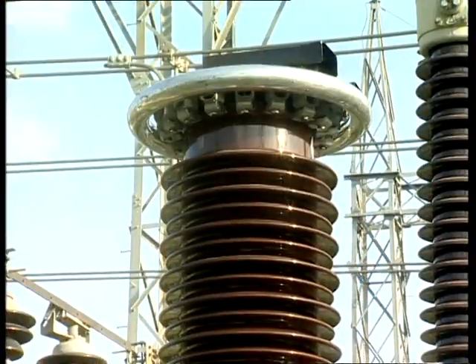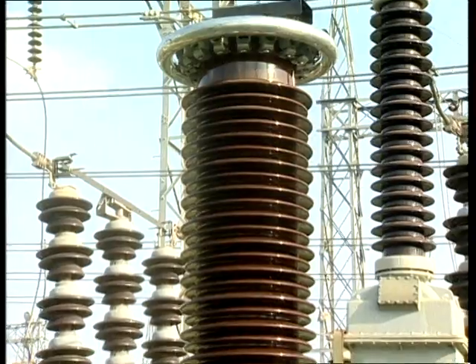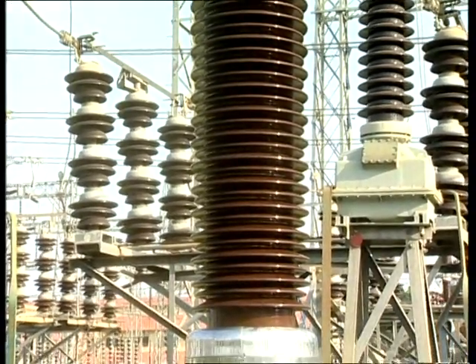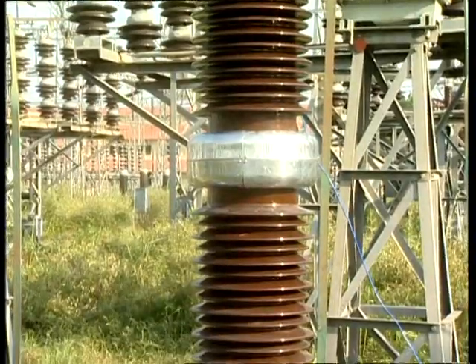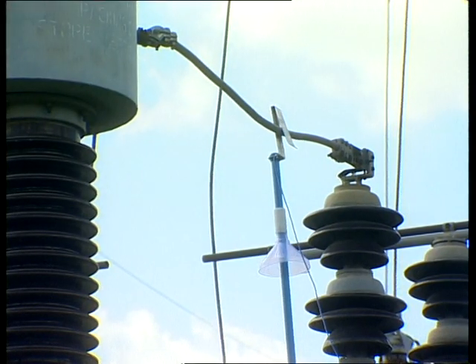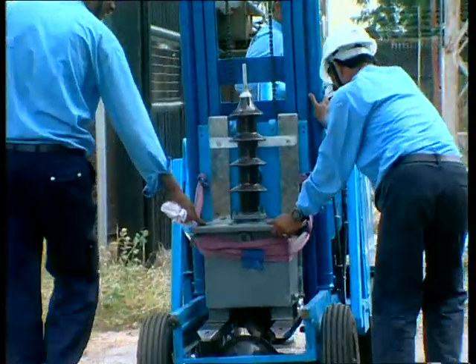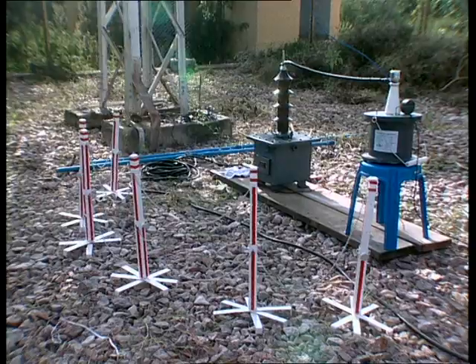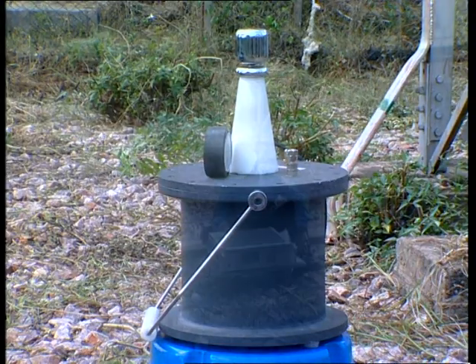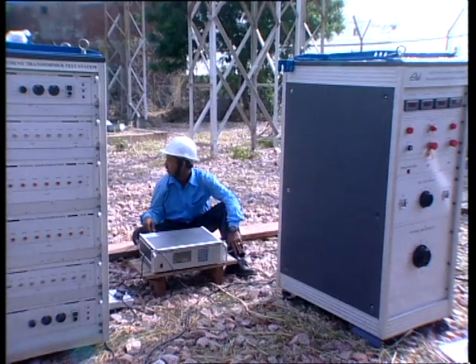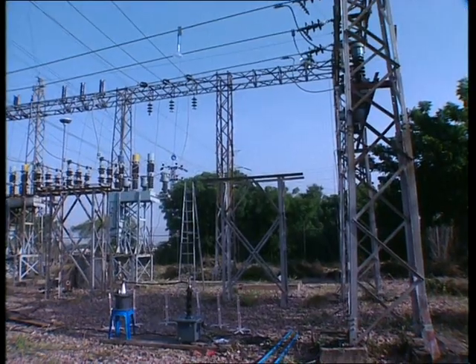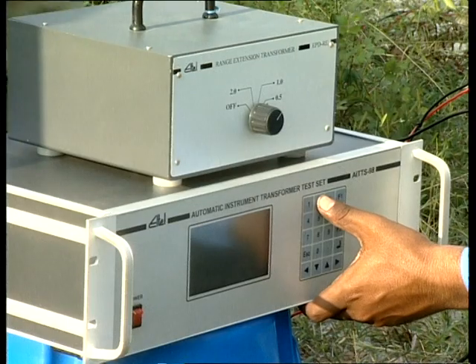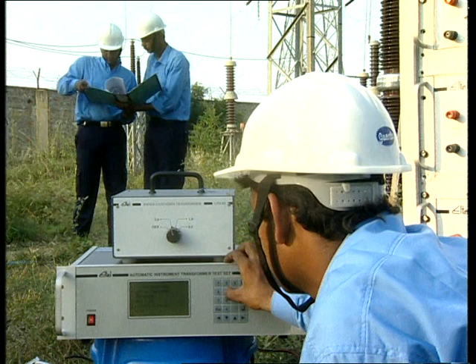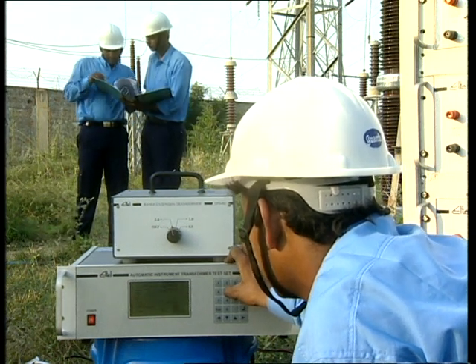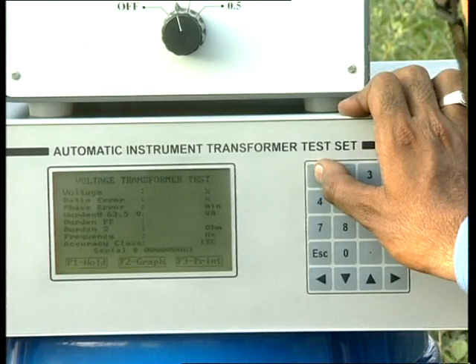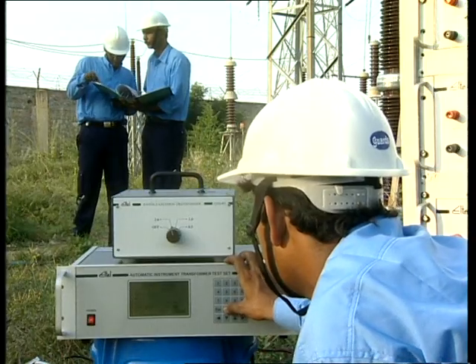Even heavy equipment such as a 132 kV capacitance divider is safely but surely lifted and moved to site and quickly but carefully assembled. MOBILAB is equipped to test and calibrate voltage transformers or VT up to 132 kV using a standard capacitor divider connected directly online. Voltage transformers up to 33 kV are tested using control source. A very high precision electronic voltage divider compares the actual source voltage against the voltage produced by the VT under test with an accuracy of 0.08%. All tests are carried out at the actual operating burden of the voltage transformer, and the test results thus reflect the true errors in the installed system as a whole.